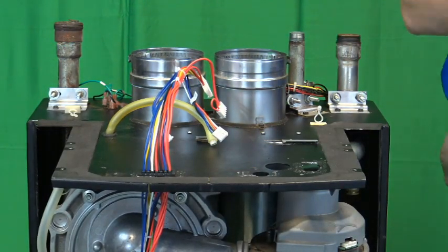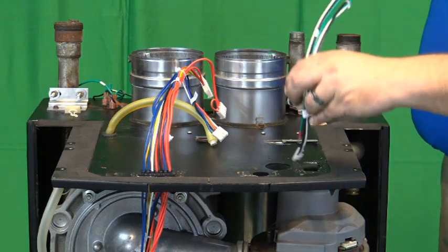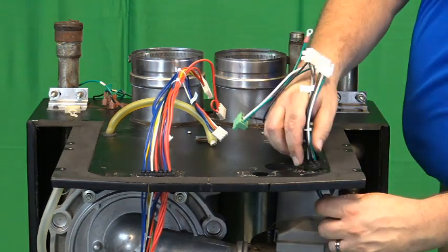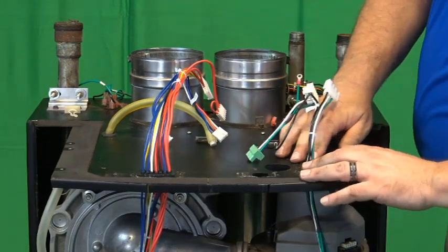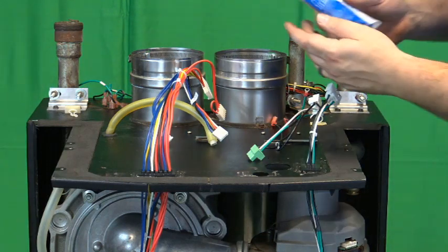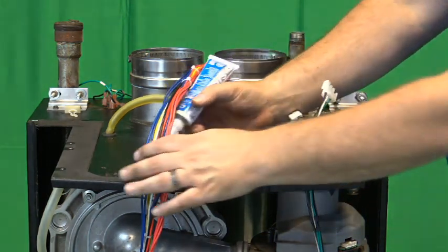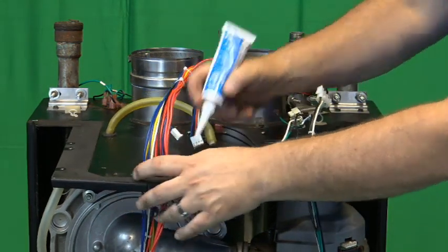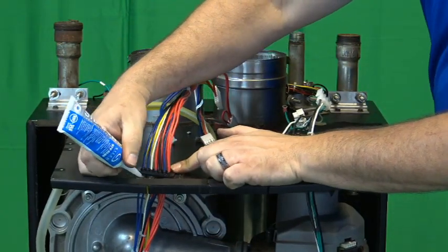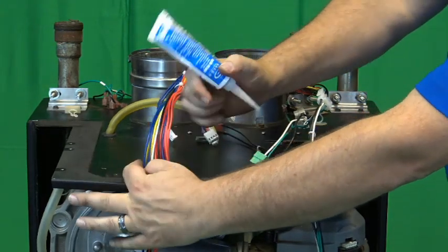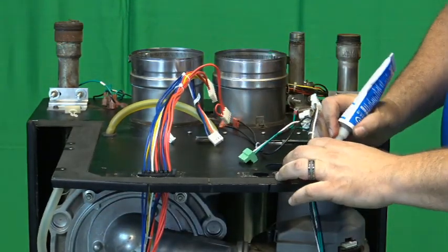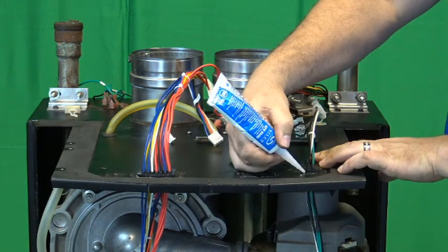We will then use the silicone provided and put a generous bead under the lip. We would put a generous bead right around the outside. This does need to be sealed because it is a sealed combustion boiler.